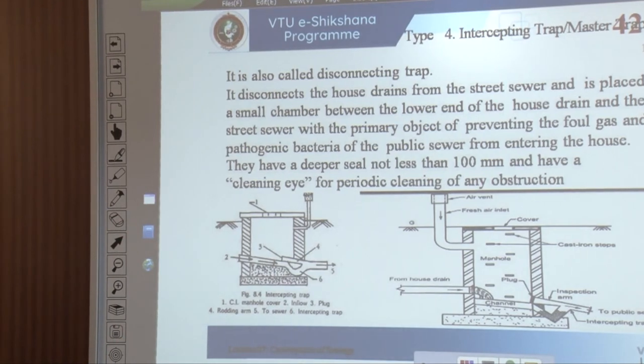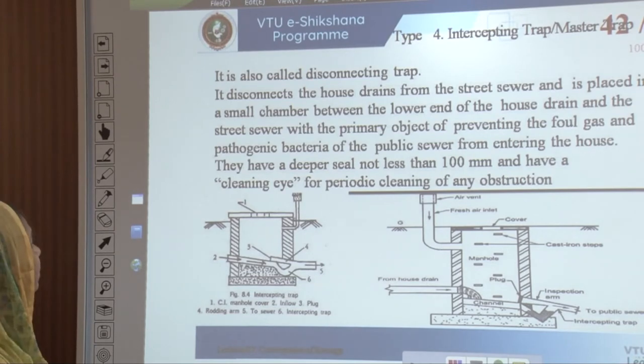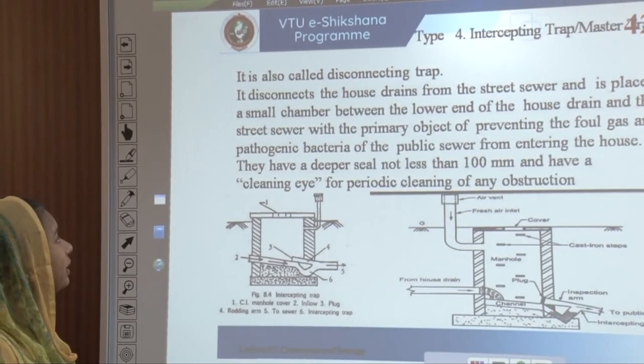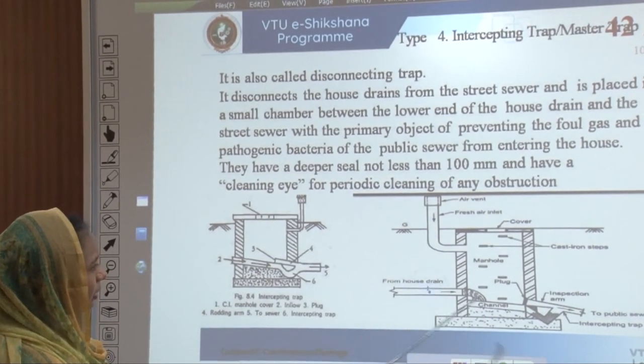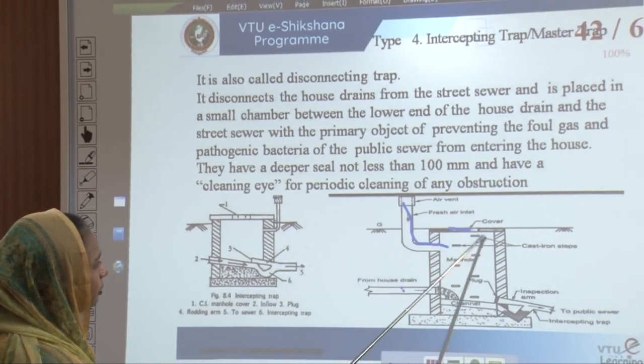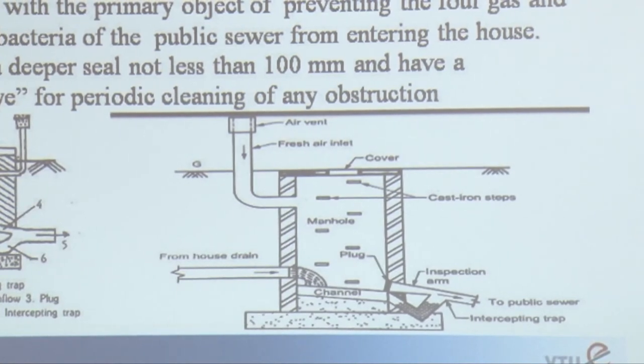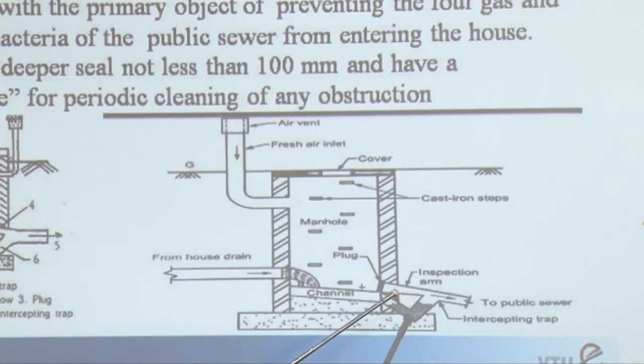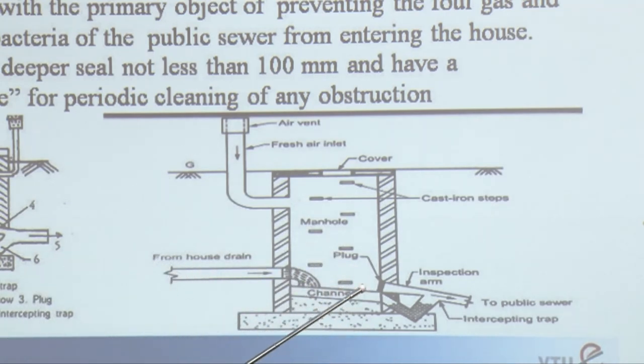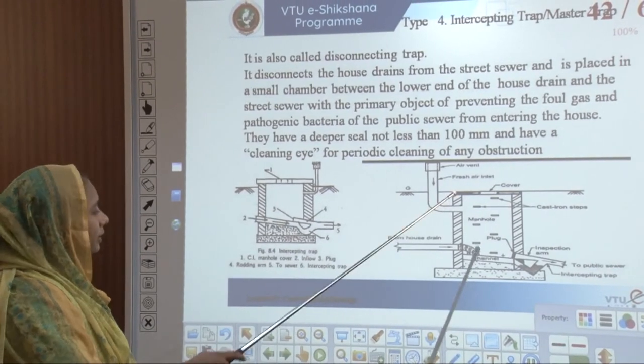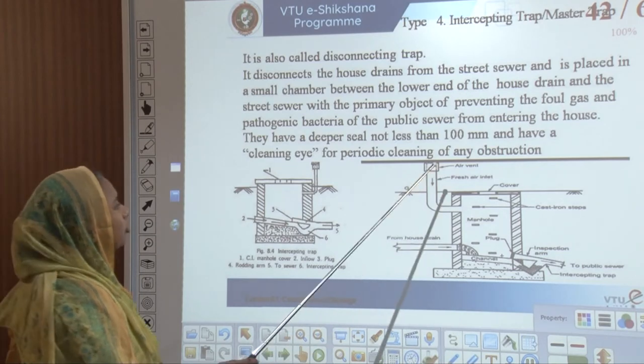The intercepting trap or master trap is also called a disconnecting trap. This disconnecting trap disconnects the whole house from the street sewer and is placed in a small chamber between the lower end of the house drain and the street sewer. An interceptor is provided so that foul gas and pathogenic bacteria do not enter the house. It has a deeper seal of not less than 100 mm and has a cleaning eye for periodic cleaning.